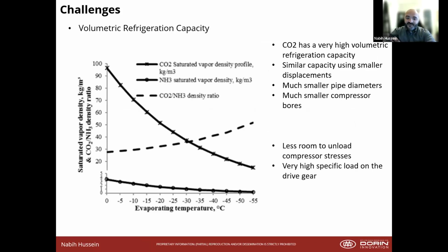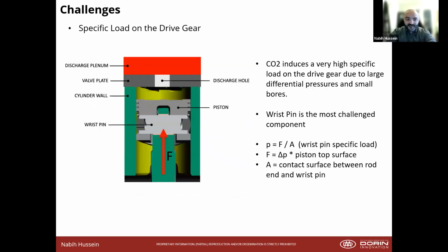CO2 has the high volumetric refrigeration capacity, which if you have more refrigeration capacity, you can have smaller pipes, smaller bores, but that has less room for the stress unloading, and that increases your specific load. So the positive comes with a drawback, and that drawback is visualized here. You have your discharge plenum, your valve plate, your cylinder wall, and that piston is connected to the rod by that wrist pin. And that wrist pin is what takes most of that specific load. So something as small as a wrist pin needs to have a lot of design thought behind it in a CO2 compressor.